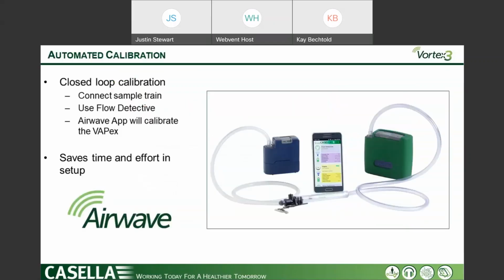Here we go. So on the closed loop calibration, you can actually use your media and do an A to Z, and it's the only calibrator that I know on the market and system that I know that actually measures the full degree of pulsation as well. So that way you can kind of ensure, okay, within the sample train attached, am I actually doing a true calibration? So the Flow Detective works nicely with Airwave and also complements the rest of our line and our portfolio of the pumps.